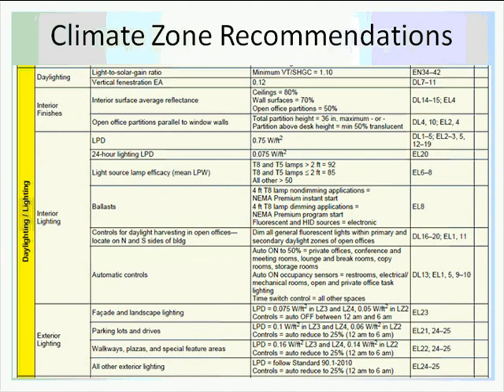Another additional requirement is reducing the 24-hour lighting. One of the major nighttime uses we see is lights that are left on to provide emergency egress when the building is actually unoccupied. According to NFPA 101 and the NEC, as long as the building is unoccupied, you don't have to meet those requirements. And there are ways to do it so that if someone's in the space, like with an occupancy sensor, the lights will be on in those areas. Often it's well overlit for the emergency egress lighting. We're not talking about the emergency exit signs. We're talking about the general lighting that allows you to walk out of the building in a non-emergency mode. Of course, in emergency mode, the lights have to be on for the required time.